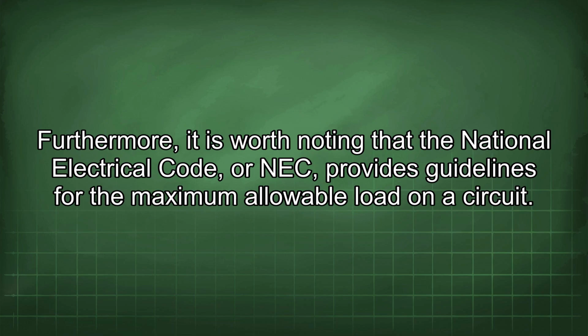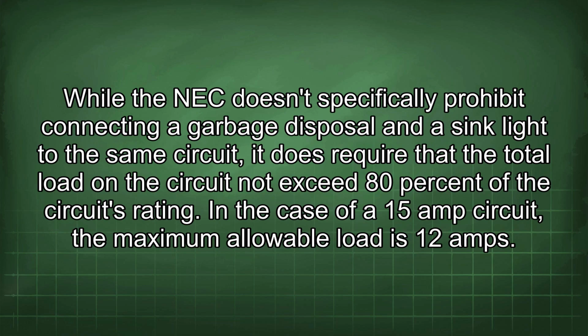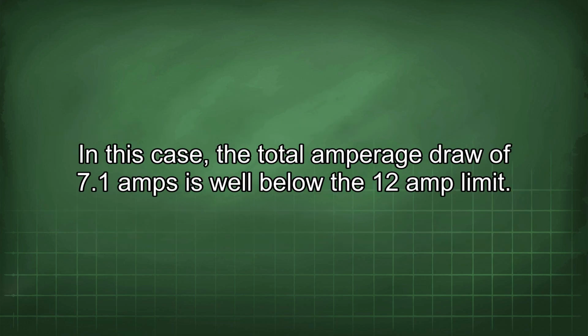Furthermore, it is worth noting that the National Electrical Code, or NEC, provides guidelines for the maximum allowable load on a circuit. While the NEC doesn't specifically prohibit connecting a garbage disposal and a sink light to the same circuit, it does require that the total load on the circuit not exceed 80% of the circuit's rating. In the case of a 15 amp circuit, the maximum allowable load is 12 amps. In this case, the total amperage draw of 7.1 amps is well below the 12 amp limit.